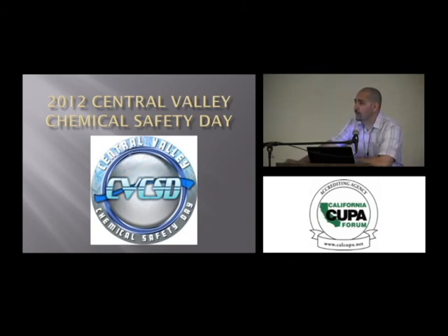Well, they should be doing sampling every year. Not the first 5 years after a plant is built. You know, you're probably going to have nothing. I've never heard of having a problem. But every year they should be looking at suspect areas: drop legs, low spots, penetrations through walls, pipes that change temperature. So you just take out a chunk. What we do is go ahead and make a few clicks there. I probably got one.